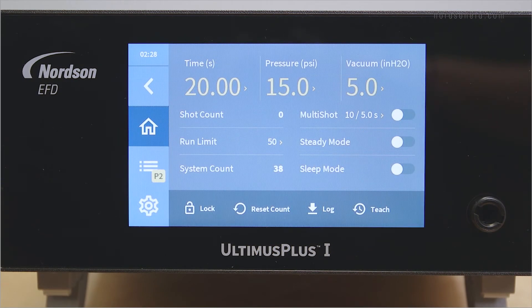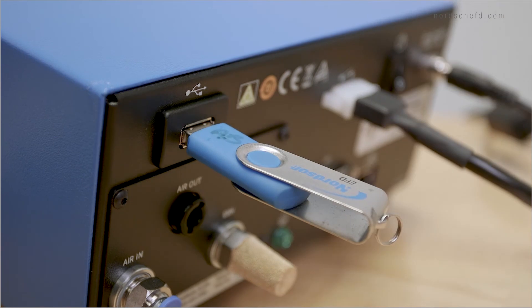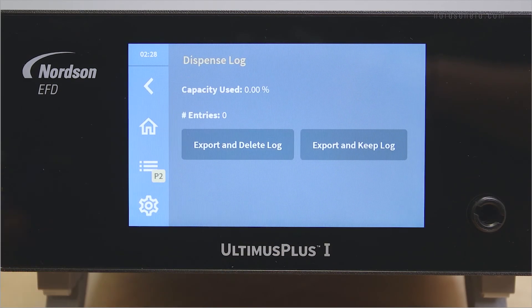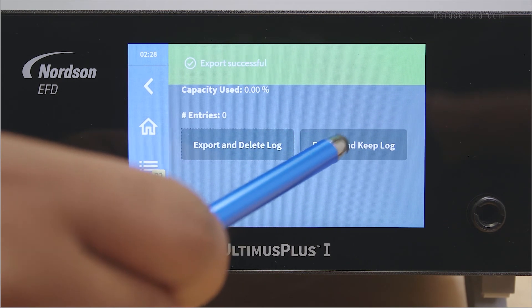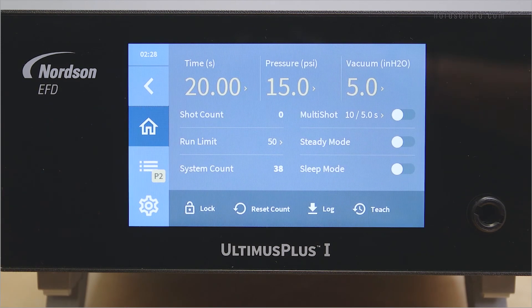Both the UltimusPlus I and II capture up to 100,000 log entries, including timestamps. To export the log, insert a USB drive into the USB port on the back of the UltimusPlus. Press the log button to bring up the dispense log screen. To delete the logs from the dispenser, press export and delete log. To continue saving logs, press export and keep log. The log files are exported as CSV files and can be opened in Notepad, Microsoft Excel, or other compatible programs.